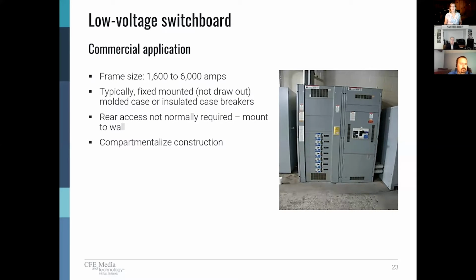So then we get into switchboards. Switchboards are different than switchgear. So what is a switchboard? Switchboards are normally available in 1600 to 6000 amps. That 1600 is a key thing. Understand that the panel boards are only going to go up to 1200 amps. If you start needing a 1600, you're going into switchboard construction.